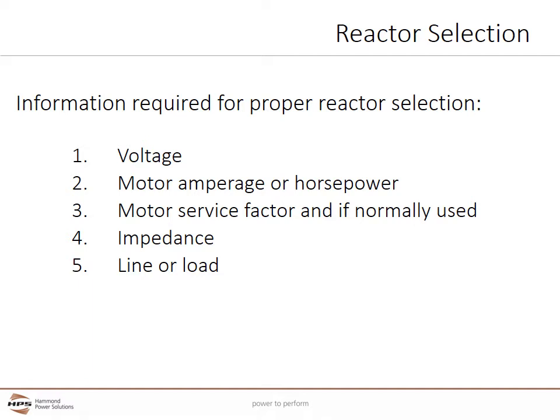There are typically five main pieces of information required for proper reactor selection. More information may be needed, but this information will typically be sufficient for many applications. Number one: the system voltage. Number two: motor amperage or horsepower. Number three: the motor's service factor and if this service factor will normally be used. Number four: impedance, typically defined as 3% or 5% in North America. Number five: will the unit be used on the VFD's line or load side?